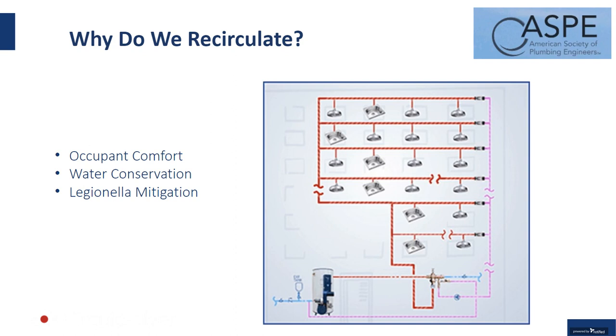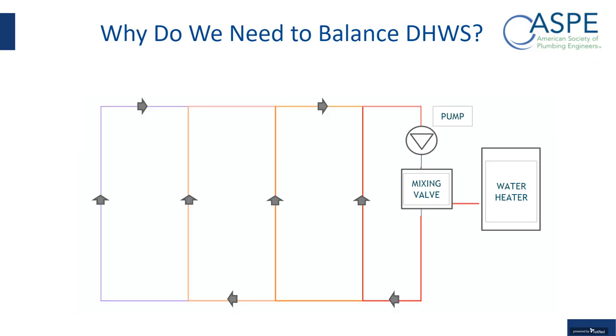Basically, if you had a building where the water heater and the mechanical room were in the basement, and you were on, say, the fifth or sixth floor, and you were the first one to turn a shower on in the morning, overnight all the water in the piping has cooled down. Now you have to turn on the shower and wait for all that cooled water to go down the drain before you start getting hot water again. So it's a lot of wasted water, and it leads to a lot of occupant discomfort. That's one of the main reasons why we recirculate the hot water.